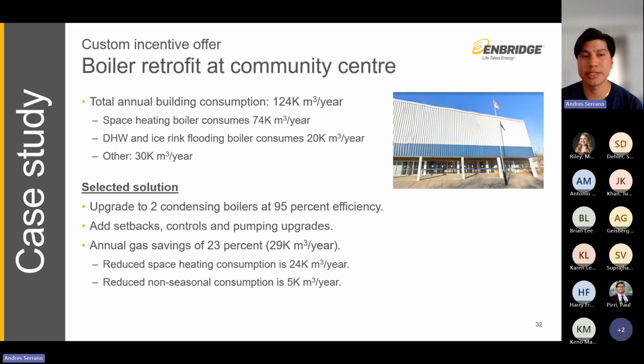The customer in this case decided to upgrade to 2 condensing boilers with 95% efficiency with the help of Enbridge Gas incentives. They also added setbacks, controls, and pumping strategies. By doing so, they saw an annual gas savings of 23%, which is equivalent to 29,000 cubic meters of natural gas per year. This is more or less a breakdown between space heating and non-seasonal.